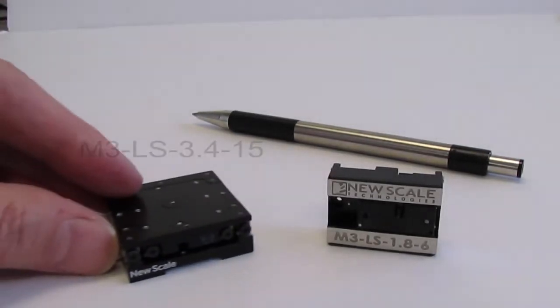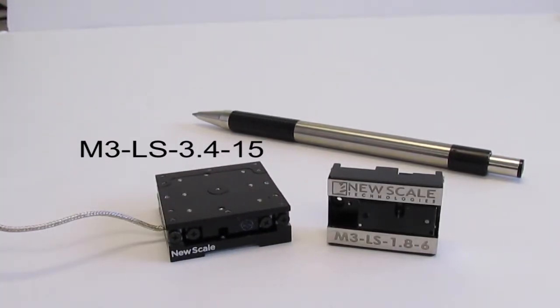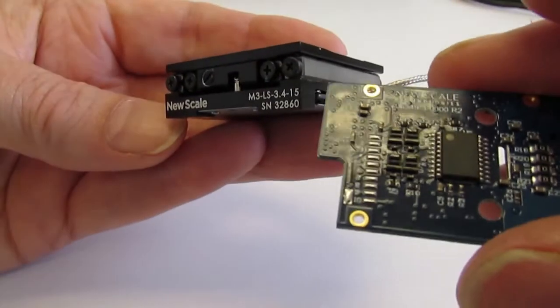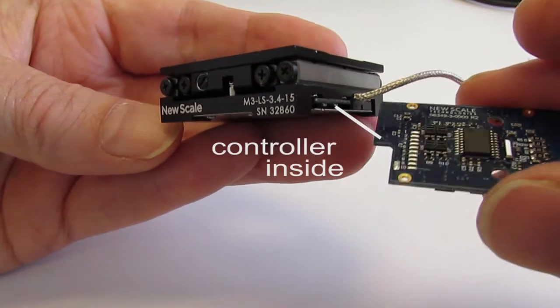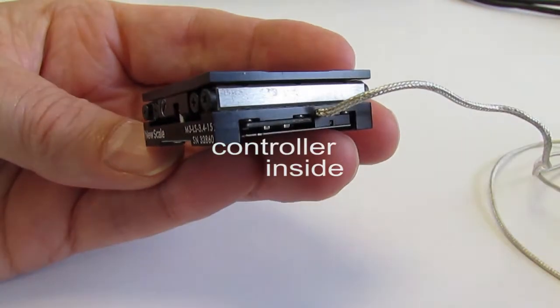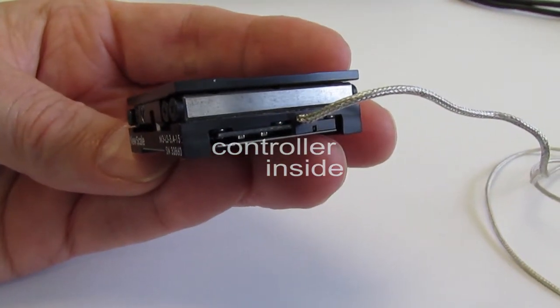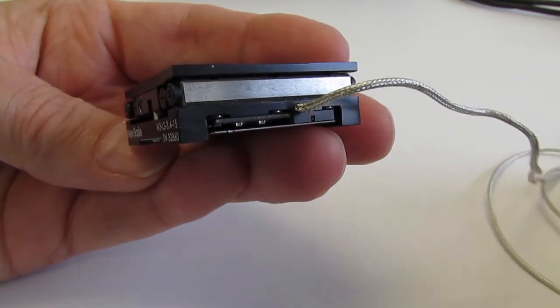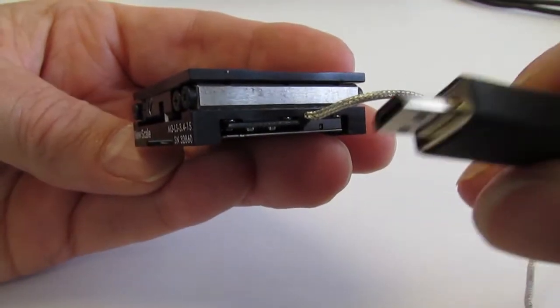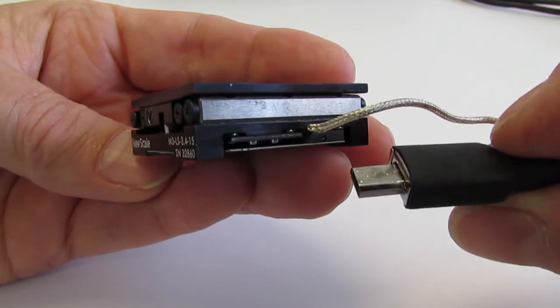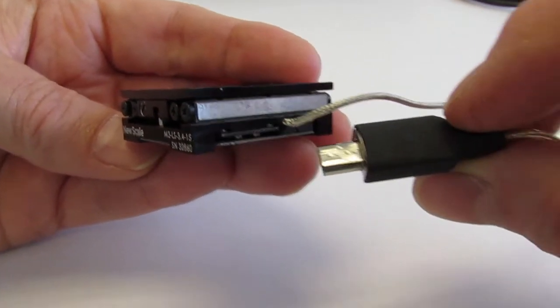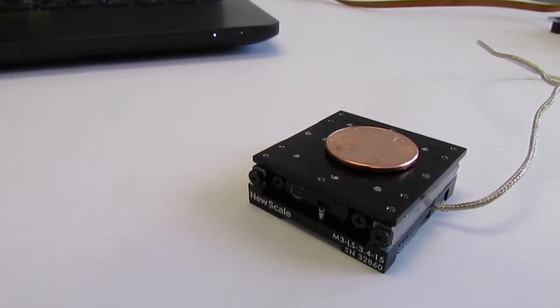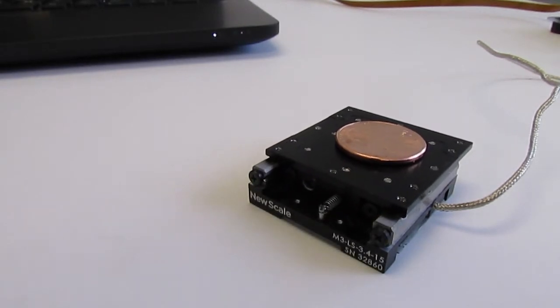Today we're introducing the M3-LS-3.4 Linear Smart Stage, the latest addition to our family of all-in-one micropositioning stages. These precision linear stages have a piezoelectric motor and all drive electronics integrated right into the stage, so there's no need for an external control box or driver card. They accept high-level motion commands directly from your PC or system processor using a standard serial interface to give you the smallest system size and fastest integration into OEM instruments.